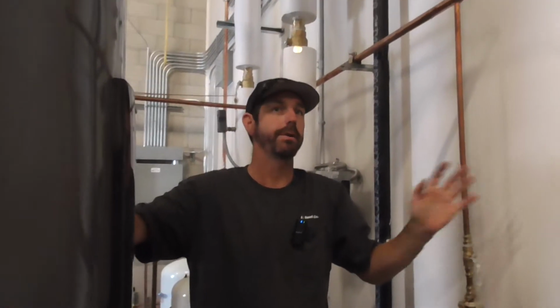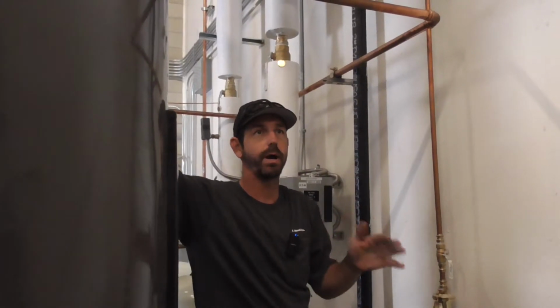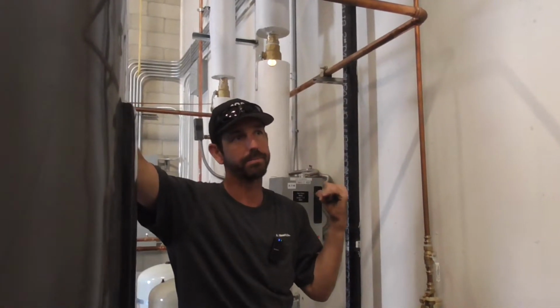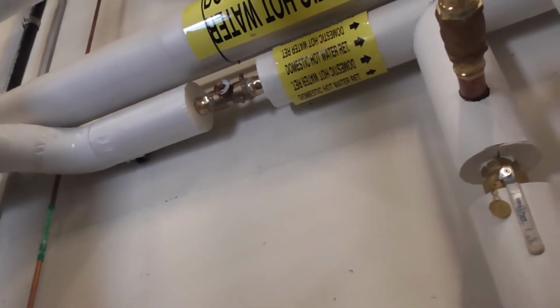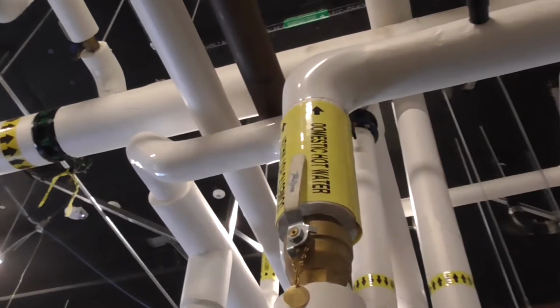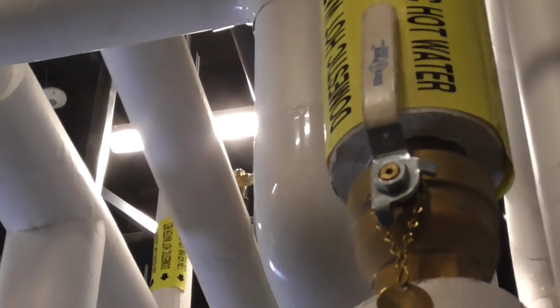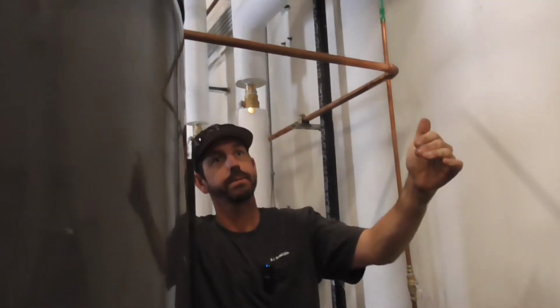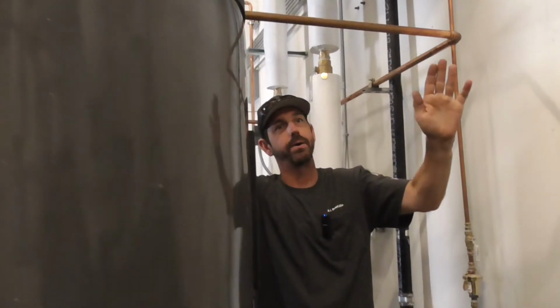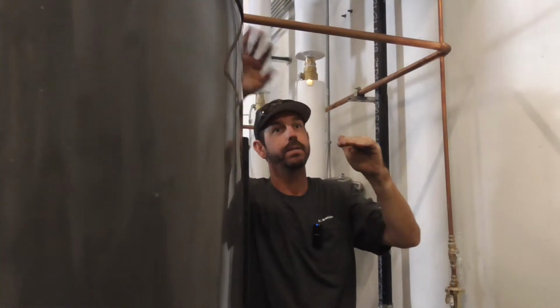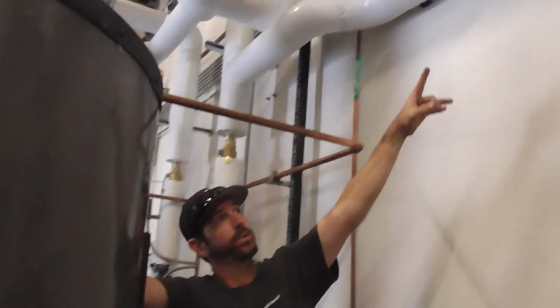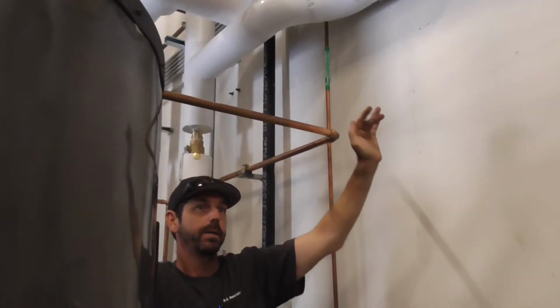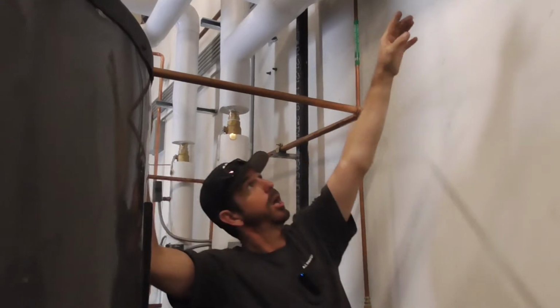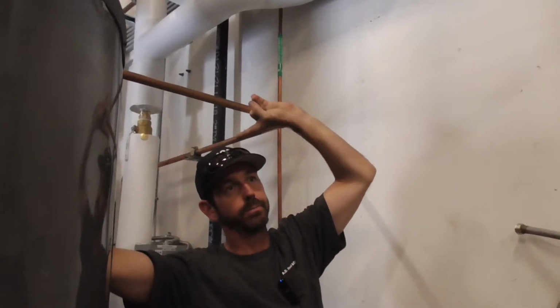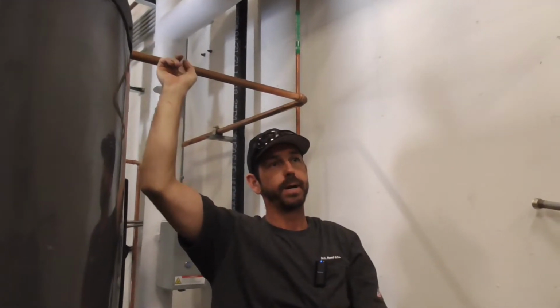So if people are in the building using water, this test can't work, okay? You have to make sure that nobody's using water in the building when you're looking at this part of the system with running the circ pump. But what you would do is open or close this balance valve, or there's another one way up high over here on the line. So if we know nobody's using the water, what I would do too is only use one of the two mixing valves when you're doing this. If the water going out is 110 and we're shooting for the 118, with the pump running, that means we have too much return water, or the return water is not at temperature yet, okay? So we can either close down this valve to push more water through the 140 loop, or open the 140 loop up, just depending on positions.